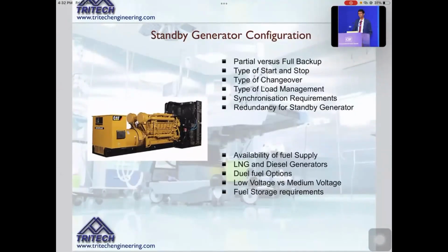So the first thing that you need to look at regarding the generator is whether it is full backup or partial backup. But in the healthcare industry, it is mostly full backup. Then you should also look at the type of start and stop, whether it is automatic, manual or semi-automatic, auto sync, all that. Then we have the type of changeover, which can be ATS or circuit breakers. And then we should also look at the load management.